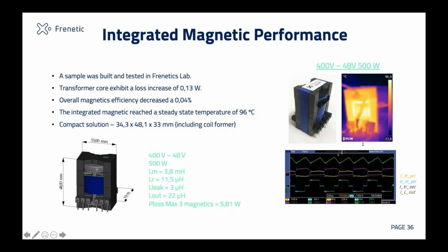Will the leakage inductance change in percent when connected to a power filter in parallel in a full bridge phase shift? The leakage inductance is part of the transformer, so it will be present in every transformer. The effect, if you connect it to the filter, depends on the connection — which configuration are you thinking about? But the leakage will not disappear.